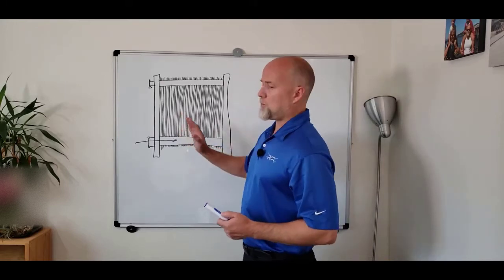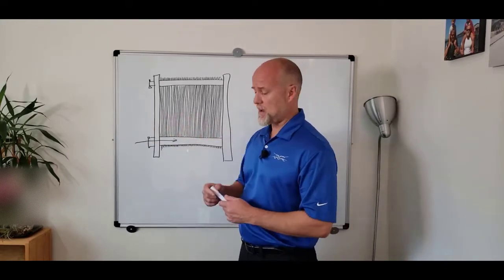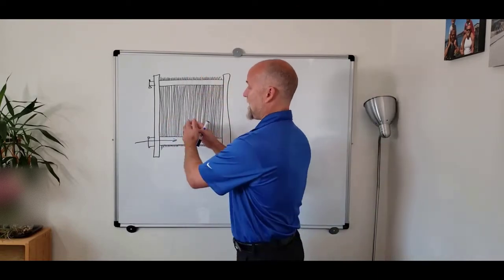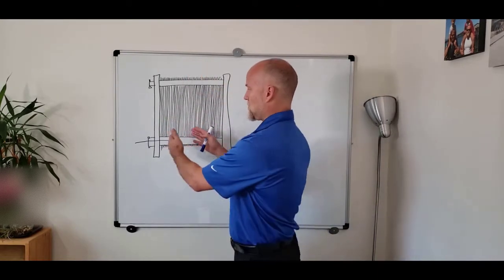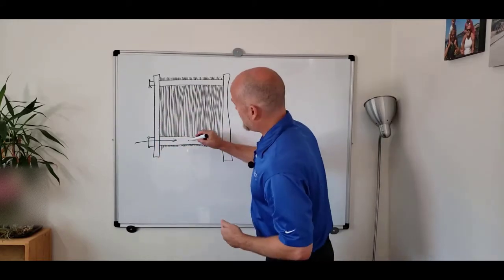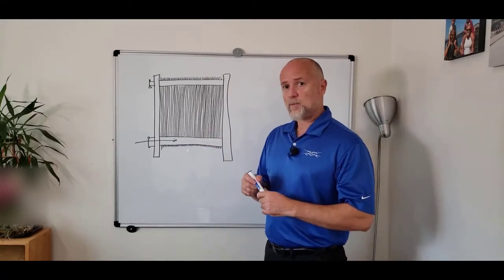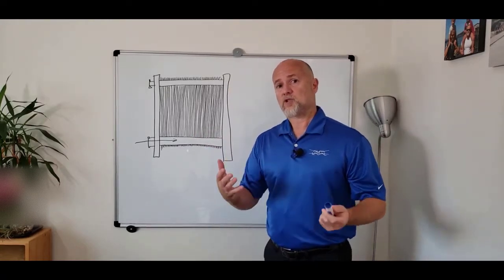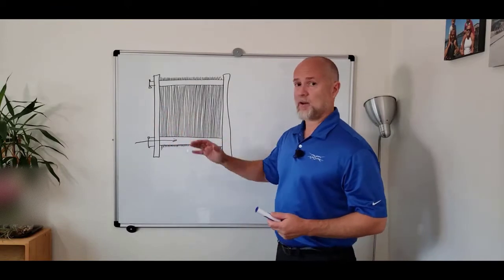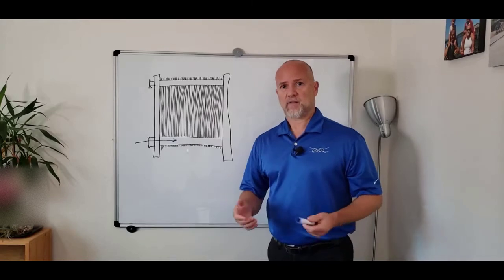If you put the higher pressure drop plates in front of the plate pack, you facilitate uneven distribution because you will have a higher flow in front and challenge reaching the end. But if you arrange higher and lower pressure drop plates properly throughout the plate pack, you minimize this effect.